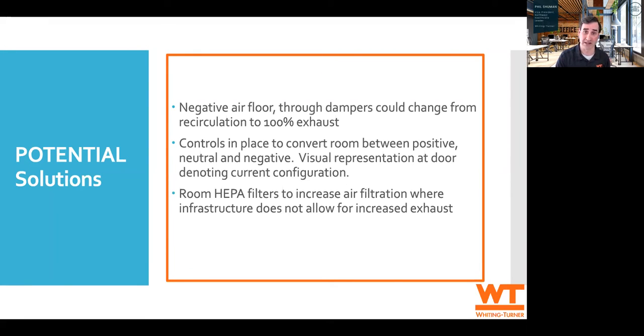You can put controls in place and do a mechanical solution that will rebalance those rooms if you already have the infrastructure in place to make sure that you're running negative. Another item that we've seen in some older hospitals, where the ceiling space and the patient room's location within the facility didn't allow for direct exhaust, was adding HEPA filters that were recirculating units. While this doesn't comply with making the room negative, it certainly added some safety for the medical professionals, as the air received more filtrations every hour.